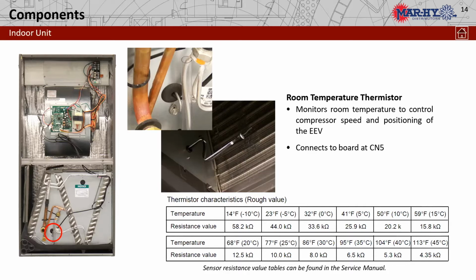You can see the little highlight down in the left corner. That is the return air thermistor, the room temperature thermistor. And you can see in an upflow position, we would be downstream, or excuse me, upstream of the coil. So we can sense the actual room temp and not coil temp, coil discharge temp.